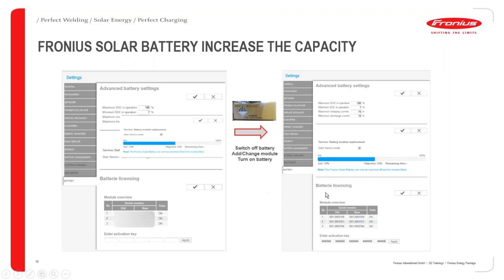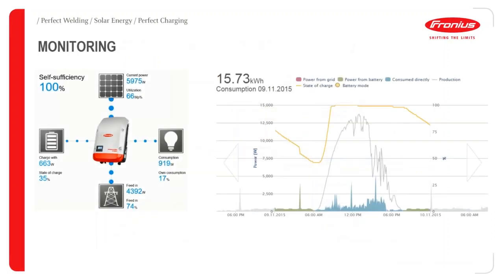To increase, if you're increasing capacity, I think I covered that a little bit before. So once you've got into the service mode, switch off the battery and add the new one to it. You can see here on the side of the battery you have your service code, your activation key, which you then put into here. So I just covered that before. So yeah, you go do the service charge. Once that's come up with okay, it's ready to do, then you put in the battery, put in the activation key, and then away you go.